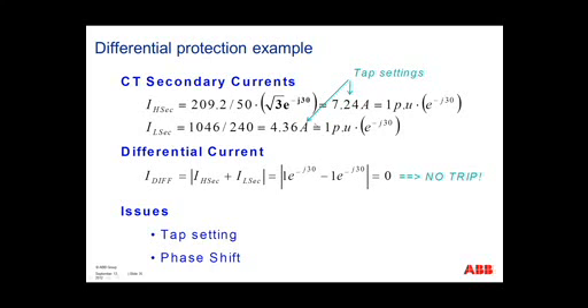One thing to notice, though, is the tap settings. Your tap settings on your high side have changed, not only by your 30 degree phase shift, but you have a square root of 3 now because of that delta connection in your CT, which affects your tap settings. So tap settings need to be accounted for, and your phase shift.